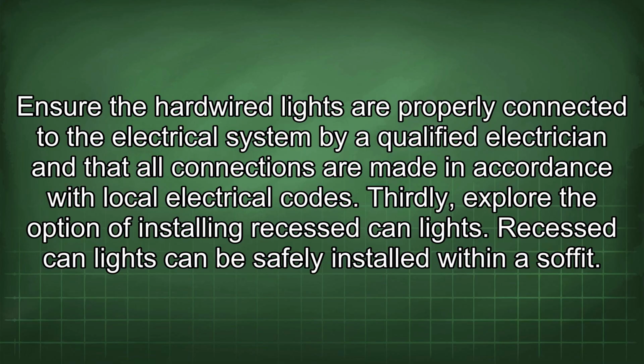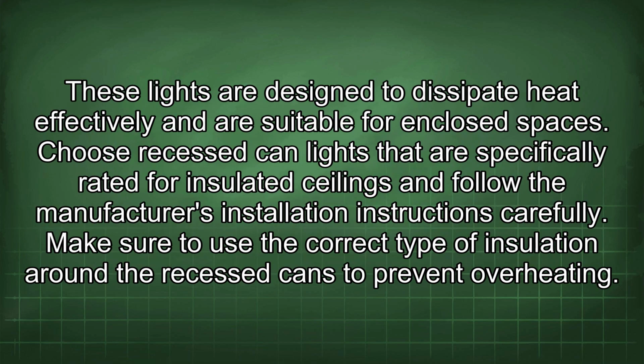Thirdly, explore the option of installing recessed can lights. Recessed can lights can be safely installed within a soffit. These lights are designed to dissipate heat effectively and are suitable for enclosed spaces. Choose recessed can lights that are specifically rated for insulated ceilings and follow the manufacturer's installation instructions carefully. Make sure to use the correct type of insulation around the recessed cans to prevent overheating.